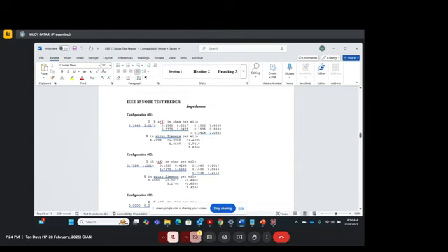Now this table also gives the microsiemens, which is admittance, right? So it's B, susceptance. And what this represents is the line charging capacitance in a distribution system.